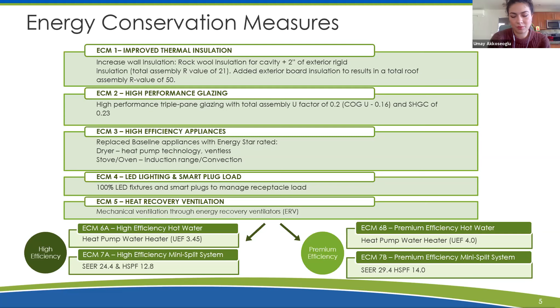We replaced this with a heat pump water heater with a UEF value of 3.45. We followed this measure with ECM7A, the high efficiency mini split system to replace the baseline package terminal heat pump system for the unit. This new system has a SEER value of 24.4 and HSPF of 12.8. For the premium efficiency pathway, we went with a heat pump water heater of UEF 4.0 and followed this with a premium efficiency mini split system of SEER 29.4 and HSPF of 14.0.